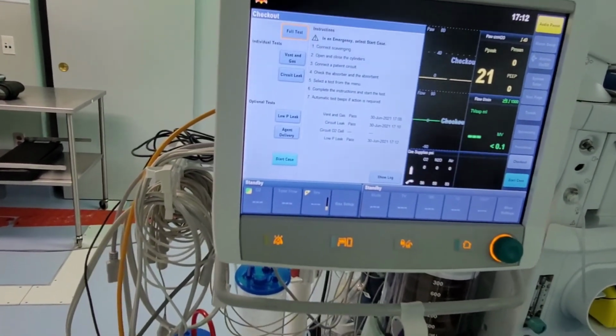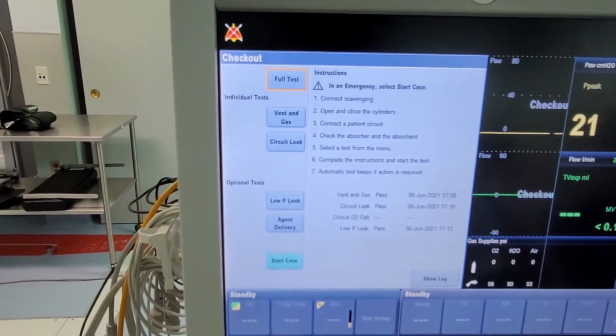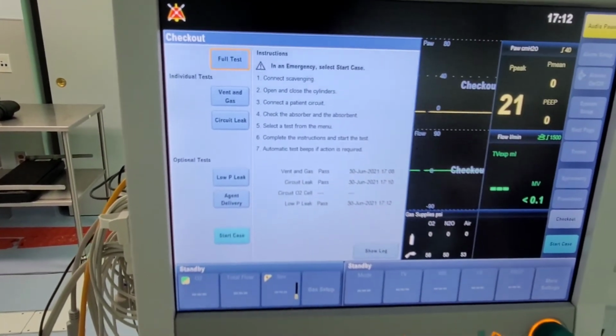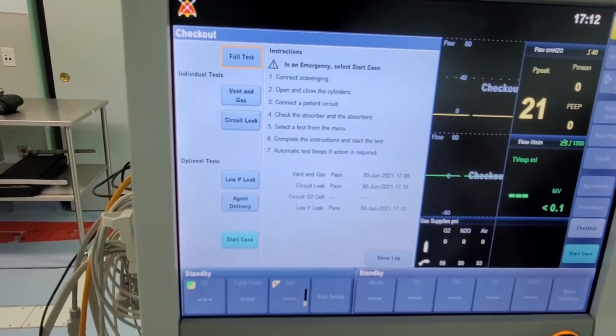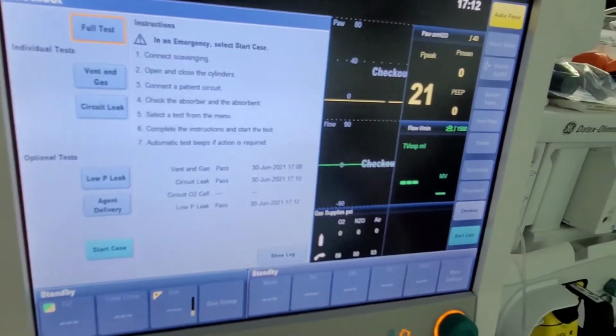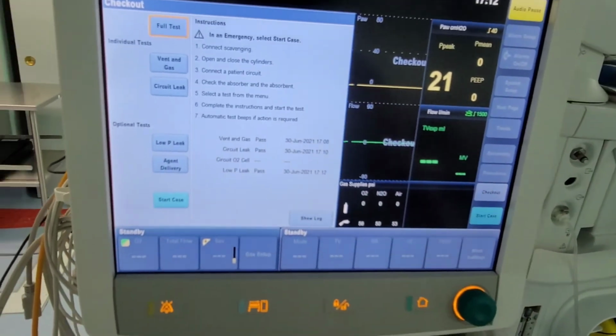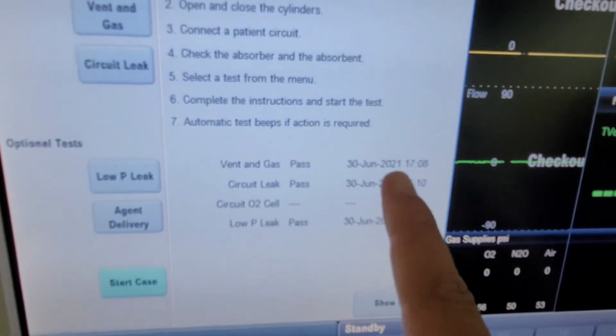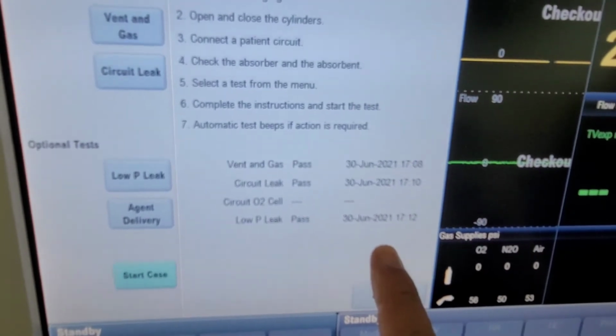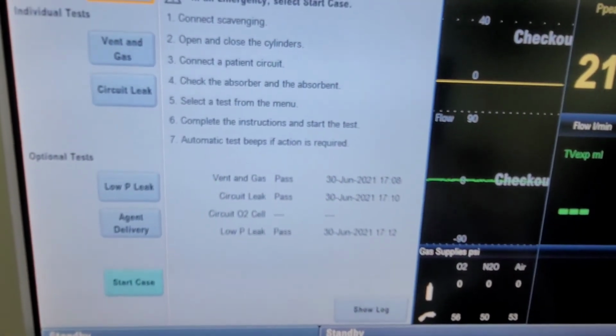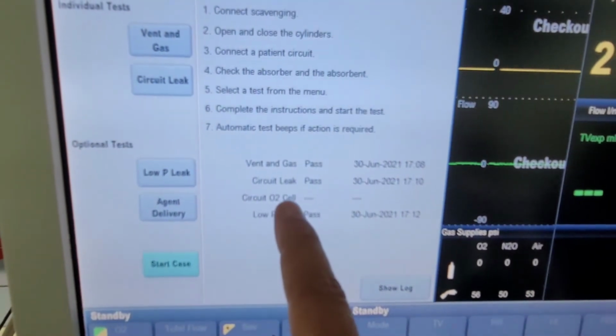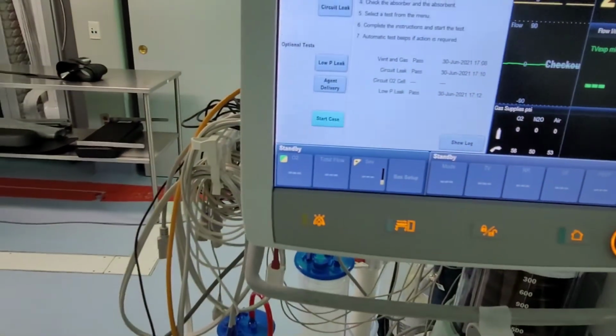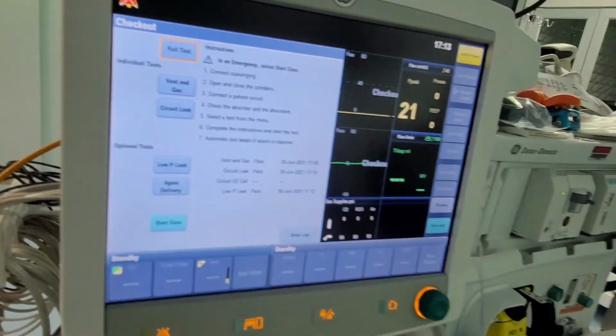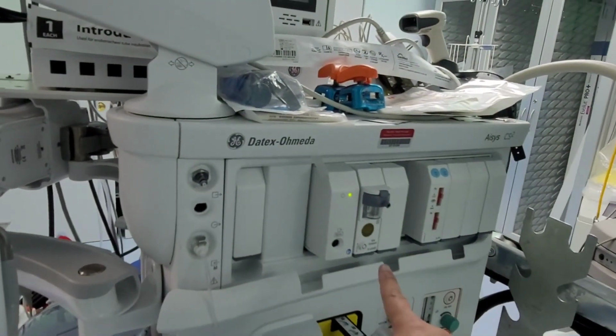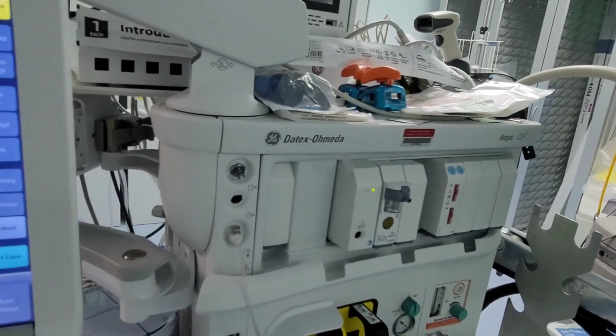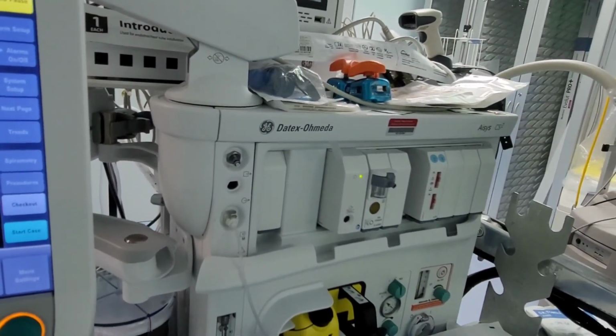So this is how you do the machine checkout, or in this case the full test, on an Aisys CS2. If an anesthesia tech, CRNA, or nurse says they've already done the full machine checkout test on this system, you can always refer to the dates on the checkout screen, and it'll tell you if and when they did that. In this case, the circuit O2 cell is not installed directly into the system because it is redundant, and they're using the external gas module, as that one reads all the gases including agents.